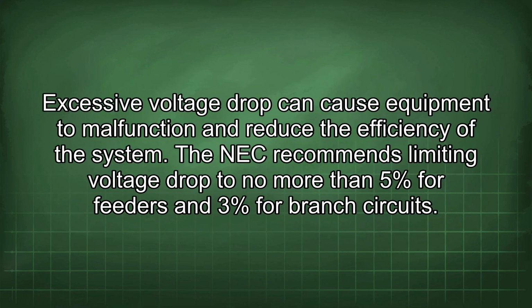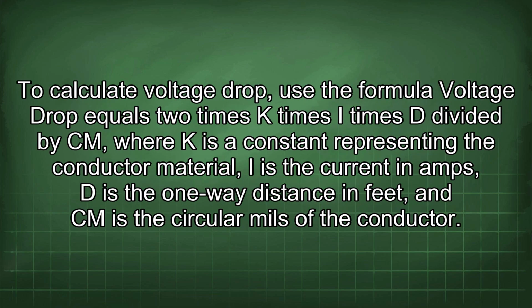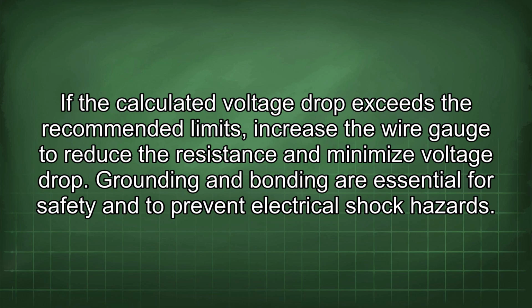Voltage drop is an important consideration, especially for long wire runs. Excessive voltage drop can cause equipment to malfunction and reduce the efficiency of the system. The NEC recommends limiting voltage drop to no more than 5% for feeders and 3% for branch circuits. To calculate voltage drop, use the formula voltage drop equals 2 times K times I times D divided by Cm, where K is a constant representing the conductor material, I is the current in amps, D is the one-way distance in feet, and Cm is the circular mils of the conductor. If the calculated voltage drop exceeds the recommended limits, increase the wire gauge to reduce the resistance and minimize voltage drop.